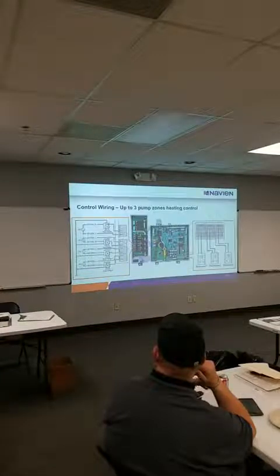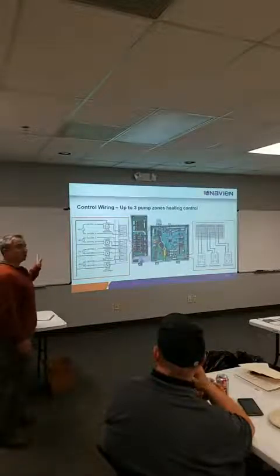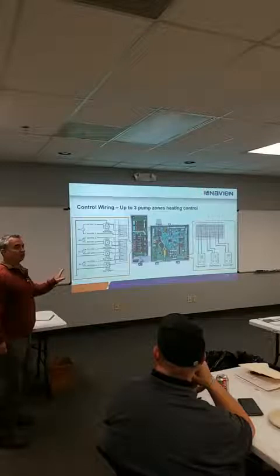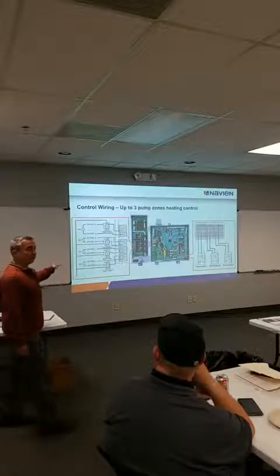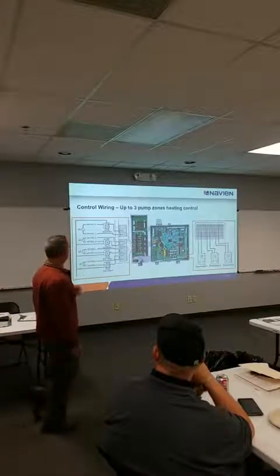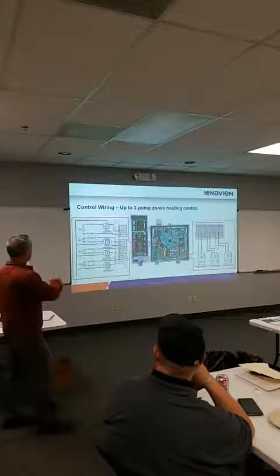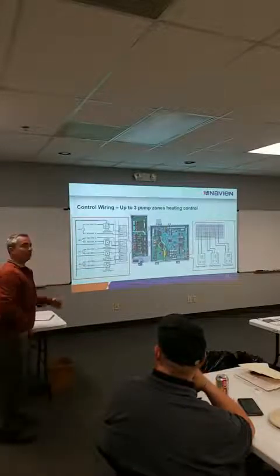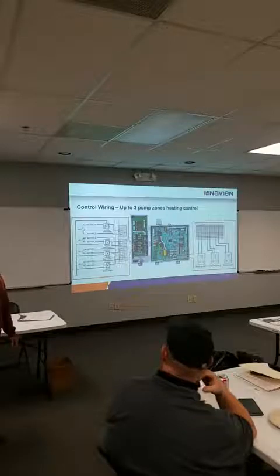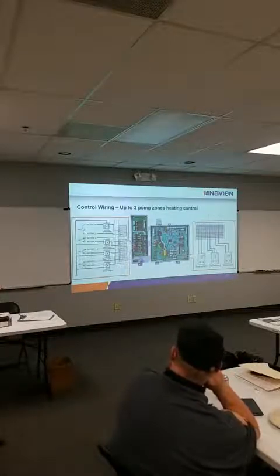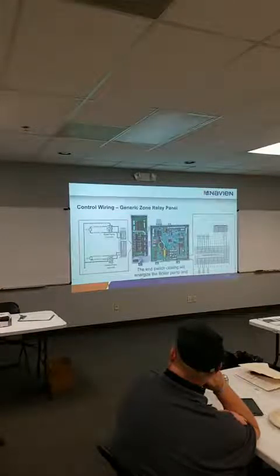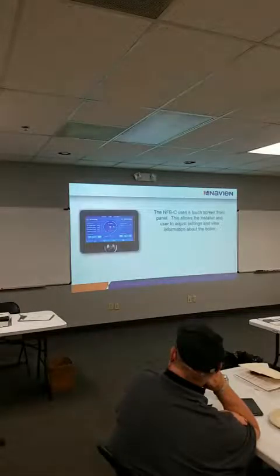So, this is one thing that really tripped a lot of people up when we came up with the commercial boiler, because they thought we were powering off these ports like we do all of our other equipment. You gotta provide power, and we're basically breaking that power on our board. So, 3 thermostats, I mean, everything else is kind of the same. That's kind of the big thing that trips you up. Again, you can use domestic hot water, you give a priority.